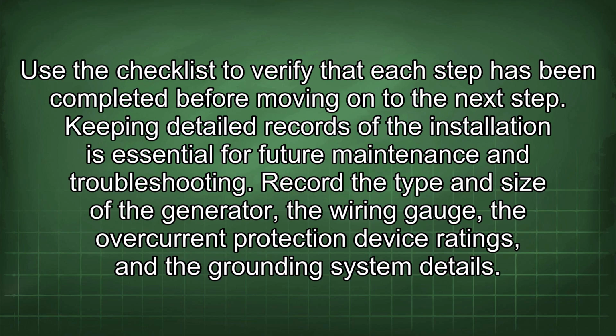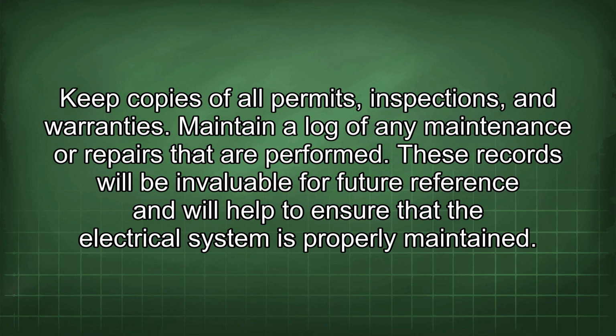Keeping detailed records of the installation is essential for future maintenance and troubleshooting. Record the type and size of the generator, the wiring gauge, the overcurrent protection device ratings, and the grounding system details. Keep copies of all permits, inspections, and warranties. Maintain a log of any maintenance or repairs that are performed. These records will be invaluable for future reference and will help to ensure that the electrical system is properly maintained.